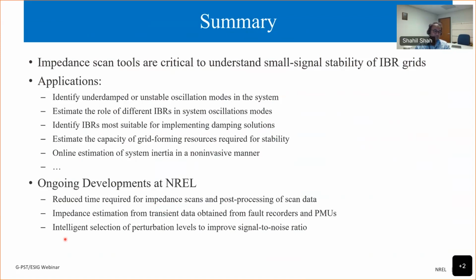So I would imagine a future where we can use all this data to get impedance responses at different nodes in the system, and the system operator can see in real time what the oscillation modes in the system are, which are arising with changing operating conditions, and how their damping is changing, so that they can take actions in real time before there is any oscillation or stability event. And last is selection of perturbation intelligently, so that we have a better signal to noise ratio.